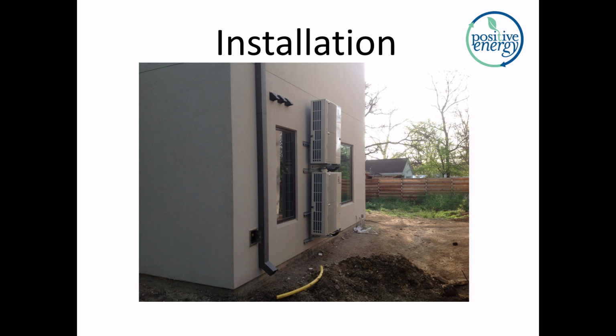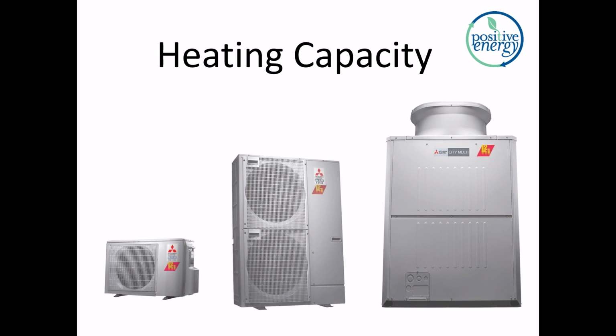These outdoor units are where most of the brains, most of the technological changes that separate VRF equipment from conventional equipment are. So these outdoor units are definitely where the complexity lies and where some of the additional expense that comes into VRF installations occurs. We talk about some of the issues at the end here, so I'll just leave it for that. Very exciting technology for those of you in heating-dominated climates. Tube-in-tube heat exchangers and the variable frequency operation allow for extended ranges of heating capacities.